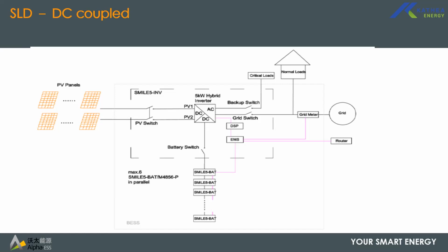And then you have your PV array, which you would wire straight from your panels. All panels in a string have to be in series. The MPPT current rating is 11 amps, wired straight to the inverter. So as I have said, as you can see, the dotted line is the inverter. So there is no need for external isolators and protection devices. The system already has built-in protection from overcurrent, string, reverse string current, earth leakage. The inverter has a built-in 30 milliamp earth leakage device. So when it gets any of those errors, it will actually log them and notify you on the portal and on the physical unit under status. You can actually access your error logs there as well.